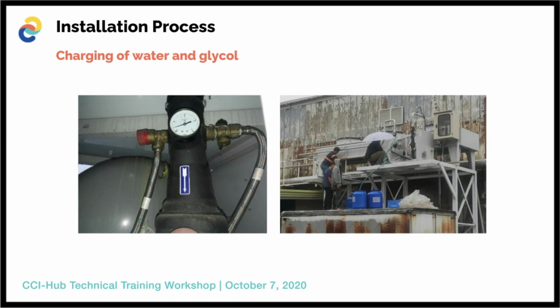This procedure uses a 50-50% ratio of mineral water and glycol in the system. Water turns into steam at 212 degrees Fahrenheit. Mixing ethylene glycol antifreeze with water in a 50-50 ratio increases the boiling point to 223 degrees Fahrenheit. We're using a food-grade glycol with anti-corrosion effects on coppers, stainless steels, and other metals. We use an external pump to charge in the mixture of mineral water and glycol in our system, and we also install air purging systems to remove air bubbles in the system.